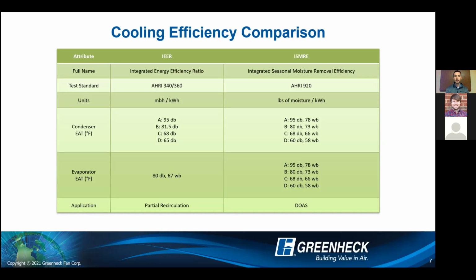unit. And if you look at the condenser entering air temps, pretty similar to the conditions that those units are actually tested at. But the biggest difference is going to be that evaporator entering air temp. So on the IEER side of things, those are always tested at 80-degree dry bulb, 67-degree wet bulb entering conditions. So there's no variation of when that air is entering that evaporator coil. It's always that 80, 67, regardless of what the actual outdoor air temp is. So yeah, the condenser is getting tested for those 95 degrees, 81.5 degrees, and so on conditions. But that evaporator is not seeing that variable conditions, which really indicates that there's going to be a high percentage of recirculation, and it's going to be pretty consistent temperatures across that evaporator coil.